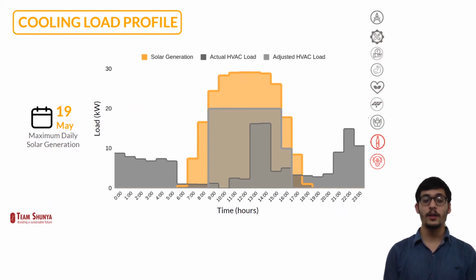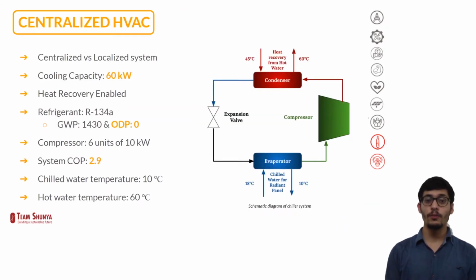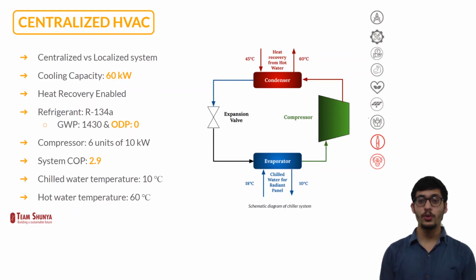and night. Thus, to achieve complete grid independency and efficient working of HVAC, we plan to run the chiller at adjusted load profile using solar PV only. So, instead of going for localized system for each room, we use a centralized system that will reduce the running cost and facilitate heat recovery.